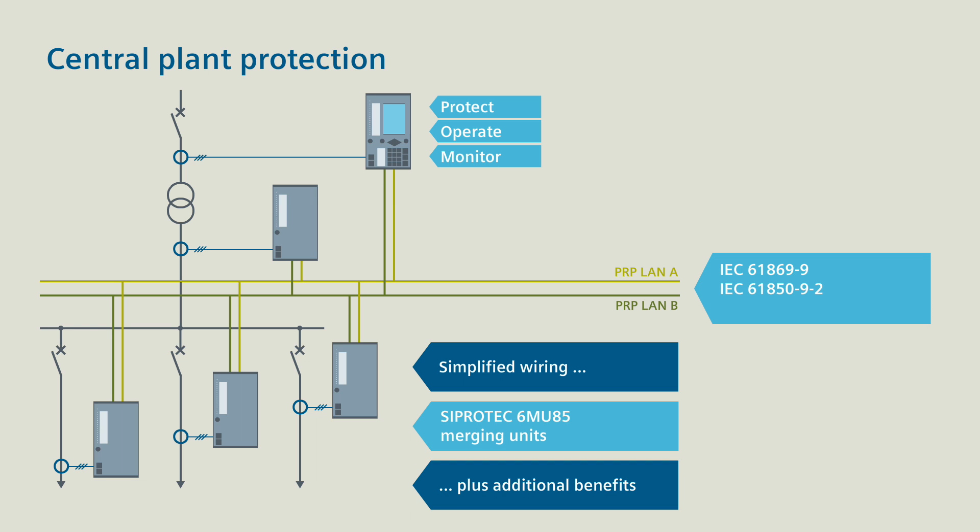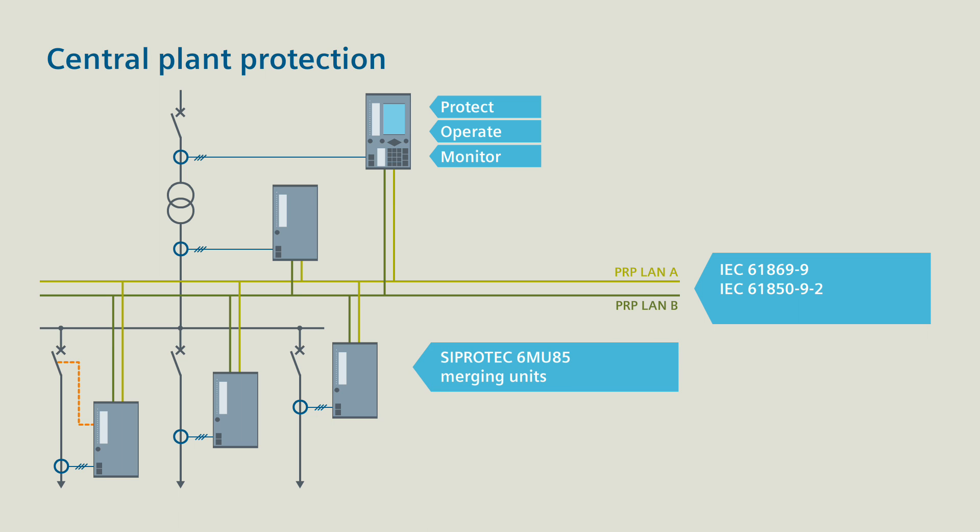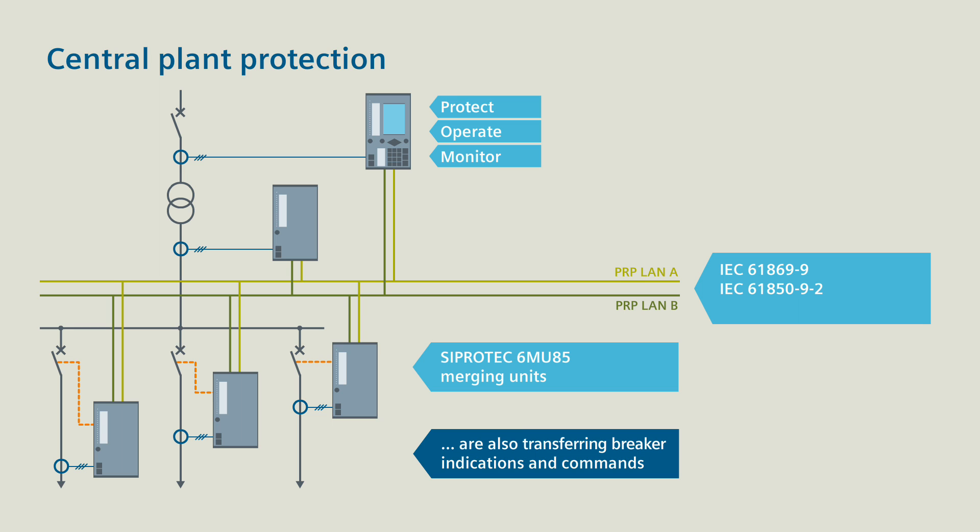In addition to significantly simplified wiring, you receive a number of other benefits. Benefit 1: Digital information, for example breaker indications and breaker commands, can also be transferred via the process bus with the SIPROTEC 6MU85 merging units using Goose.